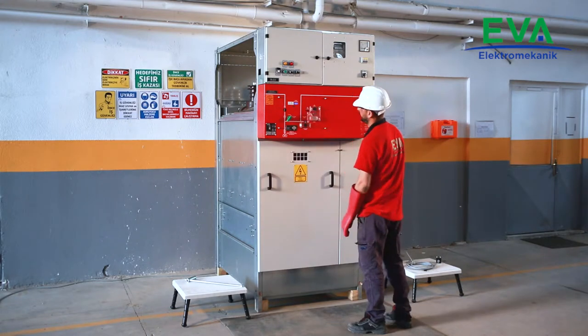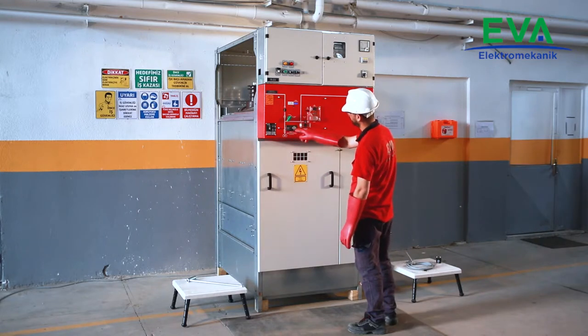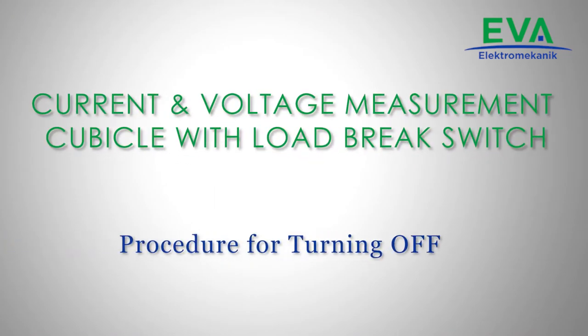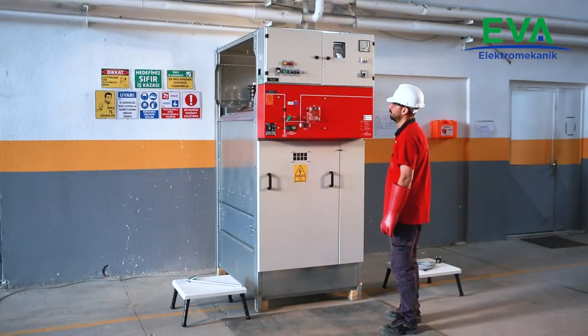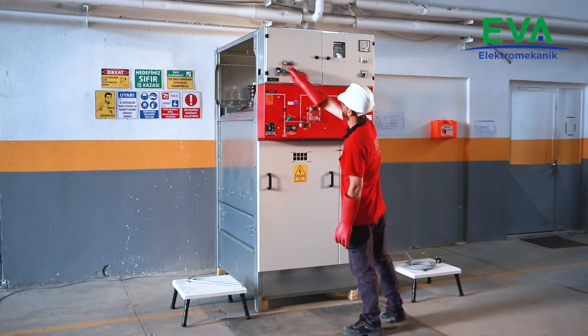Check and verify that the cubicle's outgoing is energized by observing the voltage presence indicator device. Check the gas pressure level of the load break switch from the manometer and indicator lamps. It shall be in normal state.